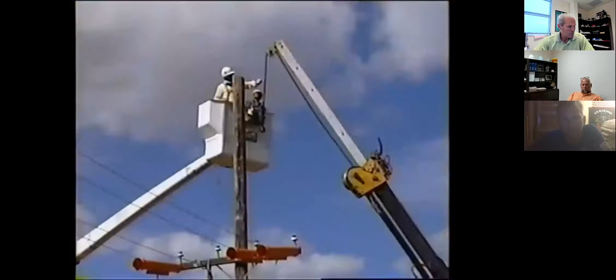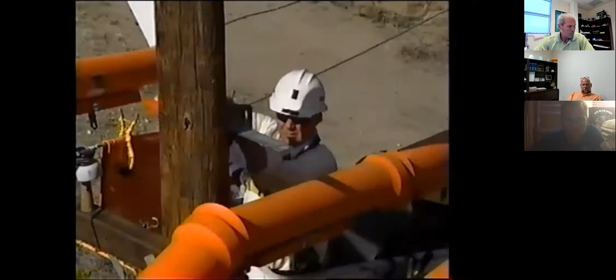The sling is attached to the winch on the boom of the line truck. The ground operator takes up the slack on the winch line in order to place a small amount of tension on the line away from the employees in the bucket. The employees in the bucket truck then make one safe and proper cut. The ground operator then utilizes the line truck to move the single section of the pole away from the employees in the bucket and lowers the single section of the pole to the ground.